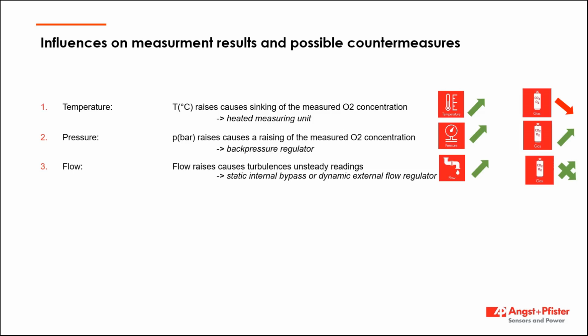but in a way that you still have a very moderate flow through the measuring cell, or you go for a dynamic external flow regulator, which is a small device where the flow can be regulated, and there you can apply from 20 to 90 liters per hour to the sensors, and it will be assured that the flow through the measuring cell will be adequate at 100 milliliters per minute, which is 6 liters per hour.